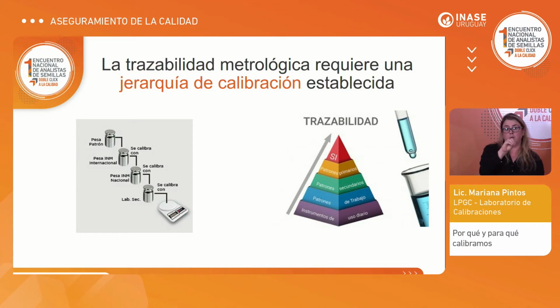The scale we use is calibrated with a weight calibrated by our lab. At the same time, this weight is calibrated with the weight of the National Metrology Lab, the LATU in Uruguay. And that one of LATU is calibrated by an international metrology institute, and that weight is traceable with a pattern weight. So there you have all the metrological traceability chain. You can see the pyramid on the right-hand side of the slide, and that's about hierarchy.